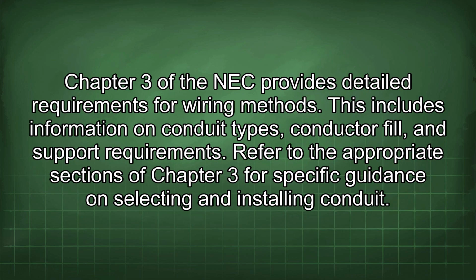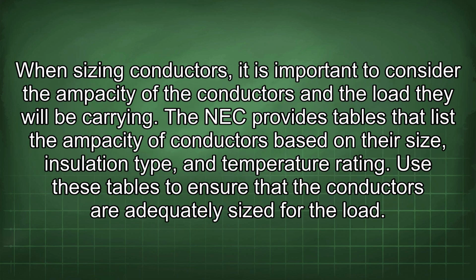Chapter 3 of the NEC provides detailed requirements for wiring methods. This includes information on conduit types, conductor fill, and support requirements. Refer to the appropriate sections of Chapter 3 for specific guidance on selecting and installing conduit. When sizing conductors, it is important to consider the ampacity of the conductors and the load they will be carrying. The NEC provides tables that list the ampacity of conductors based on their size, insulation type, and temperature rating. Use these tables to ensure that the conductors are adequately sized for the load.